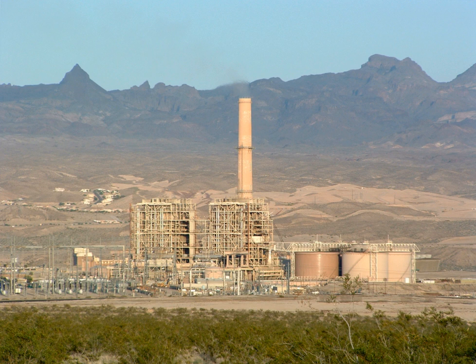Plants operating in hot climates may have to reduce output if their source of condenser cooling water becomes warmer; unfortunately this usually coincides with periods of high electrical demand for air conditioning. If a good source of cooling water is not available, cooling towers may be used to reject waste heat to the atmosphere. A large river or lake can also be used as a heat sink for cooling the condensers. Temperature rises in naturally occurring waters may have undesirable ecological effects, but may also incidentally improve yields of fish in some circumstances.